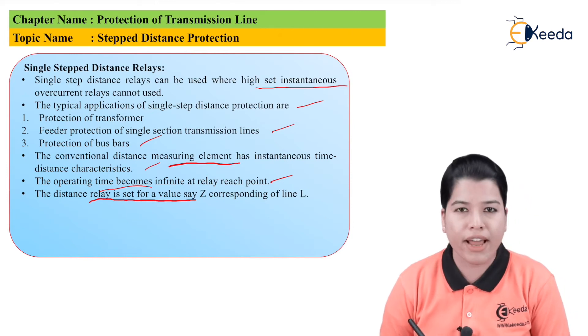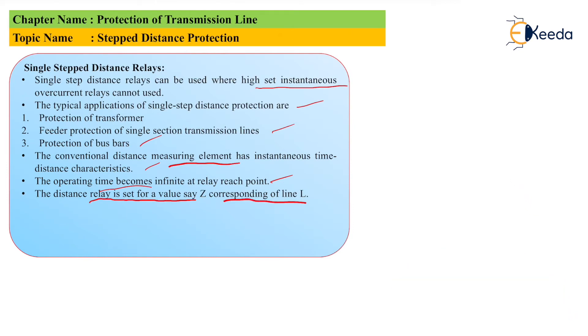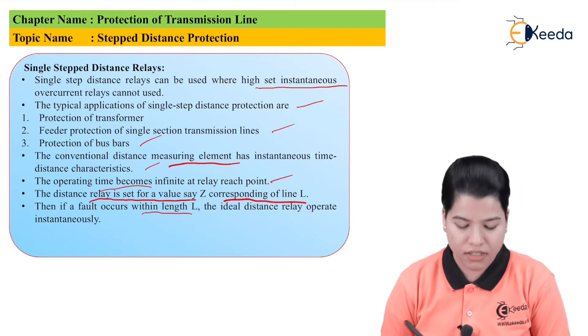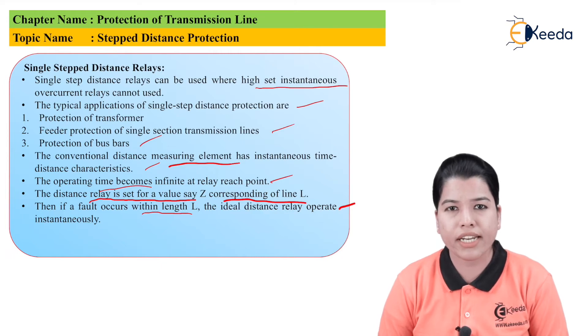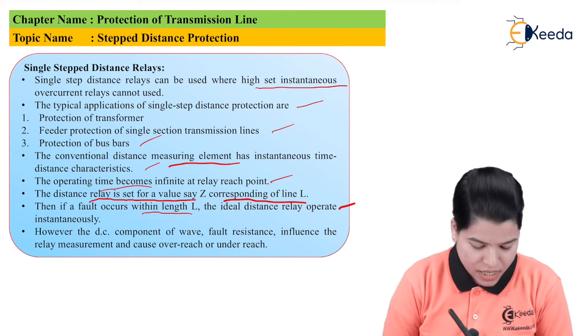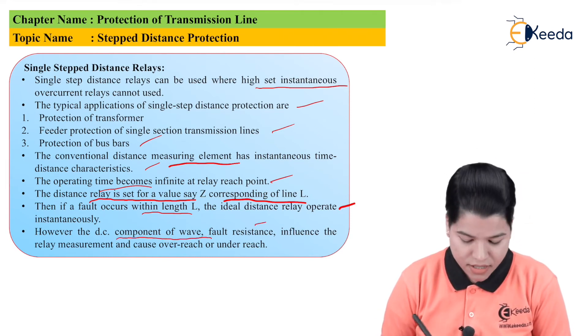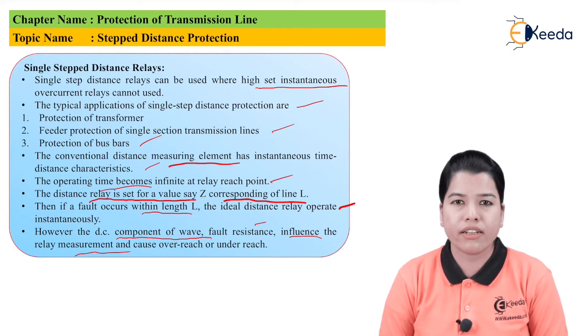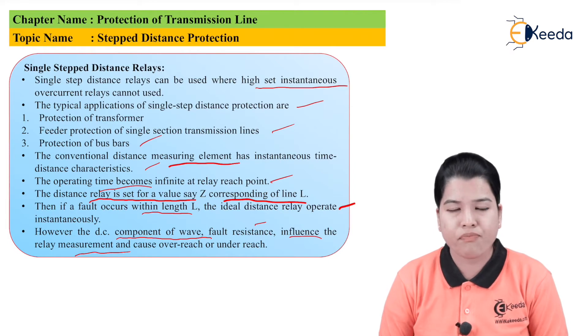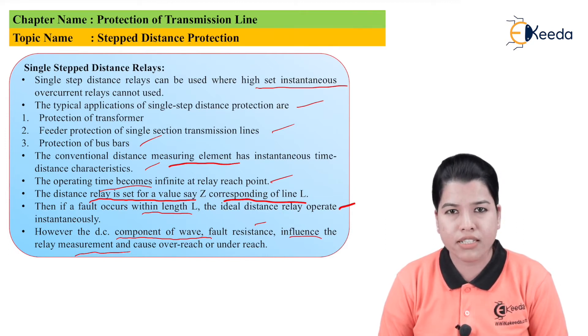The distance relay is set for a value Z corresponding to line length L. If a fault occurs within length L, the ideal distance relay should operate instantaneously, since L is the reach of the distance relay. However, the DC component of the fault current waveform and fault resistance will influence the relay measurement and cause overreach or underreach. Practically, the relay may sense that the impedance has increased or decreased due to the DC component or fault resistance.